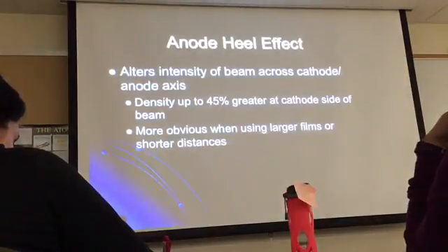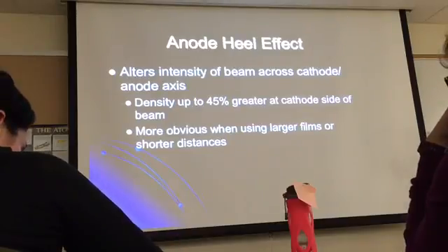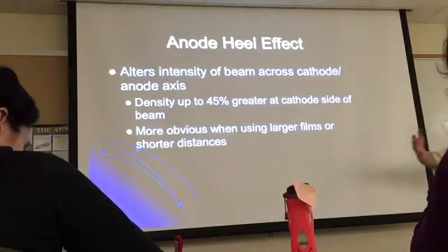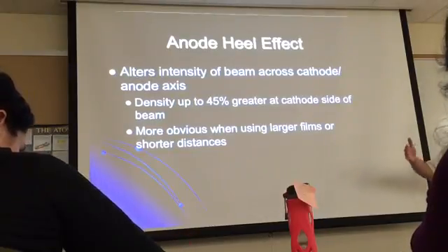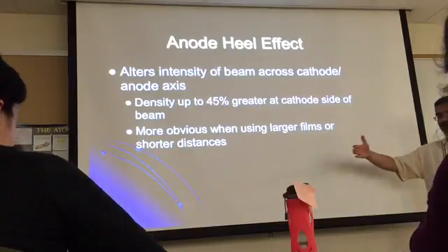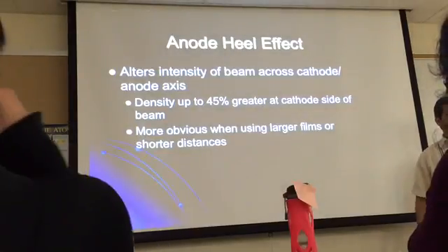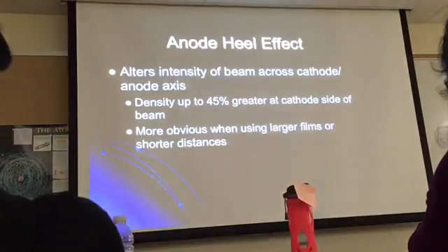Okay, more obvious when using larger films or shorter distances. If you're using, for example, a 14 by 17 and you're using the small focal spot, in a 14 by 17, you see it more easily than if you're using the large focal spot in a large distance.